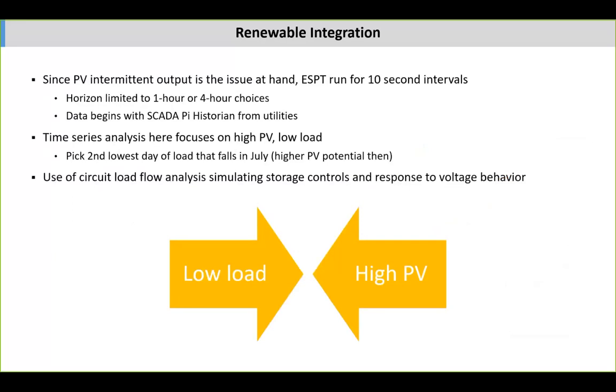When we're managing intermittency in time series analysis, we need to run the analyses down to 10-second intervals. Getting 10-second PV data is often another challenge, but there are solutions around it. It starts with SCADA data from the utilities, typically picking high PV production days with low load. And you're not only simulating the circuit behavior and the battery, but the battery controls, because the control design is critical.